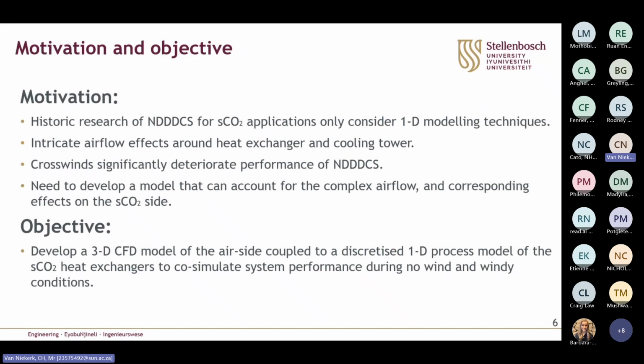So historic research on natural draft direct dry cooling systems for SCO2 applications only considers one-dimensional modeling techniques and off-design temperature operation. We've seen with detailed CFD models of natural draft cooling systems that there's a formation of recirculation, flow separation, and uneven velocity distributions over the heat exchangers, which all contribute to lower heat transfer rates, which the 1D models can't account for. We've also seen that crosswinds significantly deteriorate the performance of natural draft cooling systems, which haven't been explored for SCO2 applications.